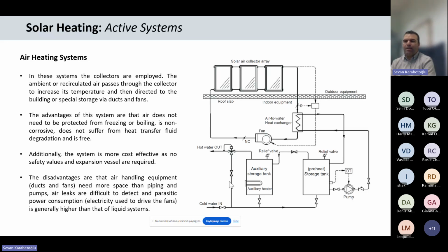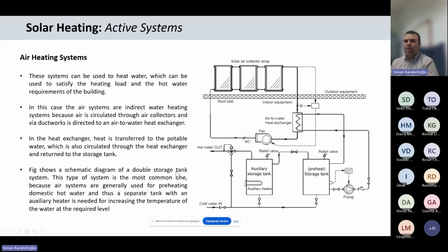But they have a disadvantage: air handling equipment like ducts and fans takes more space than piping and pumps. The hydraulic diameters are larger, of course, than for liquid circulating pipes. Therefore, the volume of the system is larger than the water circulating system. The system can also be used to heat water, not only for space heating, but the heating loads should be high, so the mass flow rates should be increased. In that heat exchanger, there will be heat transfer to the potable water, which is also circulated through the heat exchanger and returned to the storage tank.